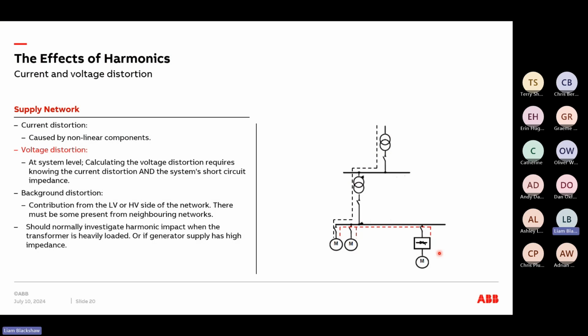So if we take the typical supply network, we've already touched on current distortion being caused by nonlinear components, switching devices. Voltage distortion is something more at a system level. Calculating that voltage distortion requires knowing what the current distortion is, but also the system short circuit impedance as well. So we have the current and voltage distortion, which I've probably not got the best way to highlight, but you can see the dashed lines to say where they typically reside within.